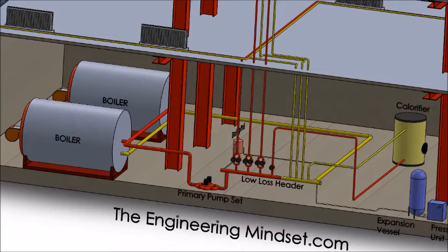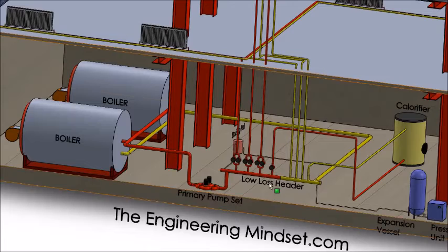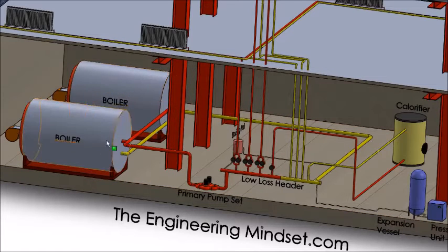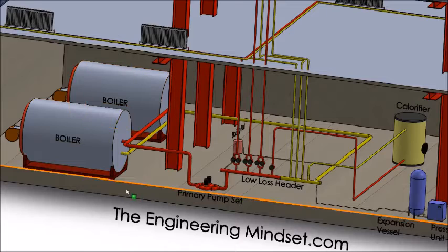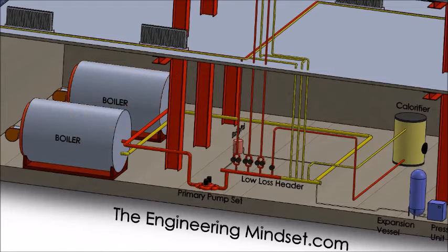Usually they won't both run at the same time. It is possible that they can. In some configurations that is needed. But then the pumps will cycle. So for 1 week it might be pump 1, and then for the next week it might be pump 2, which is the duty pump, and the other pump won't run during that time unless the duty pump receives a fault and it can no longer operate, and in that case then the standby pump will then operate and take over. So you get security built into the system in these configurations. The same with the boilers, this can work exactly the same, so both can run or individually or neither.